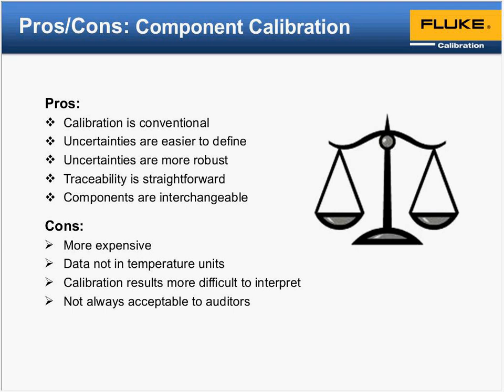All right, the next question is, do you typically check intermediate linearity points of, say, 25 and 75 percent of range? Yes. In the slides we kept it short to a 2-point cal, but it's actually very good to have interim points in between when testing. In our slides, to shorten it, 0 and 100 were the points in question. You can test in between, at 50 and 75, after you make the 0 adjustments, go back and double check. You can always check them on the way back up, and that adds a layer of robustness to your calibration.